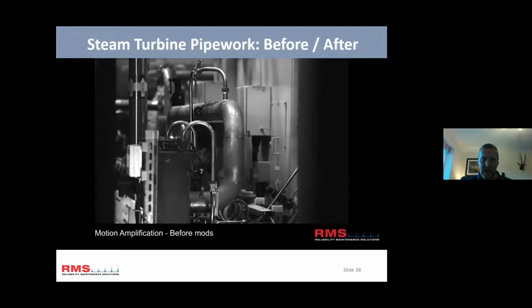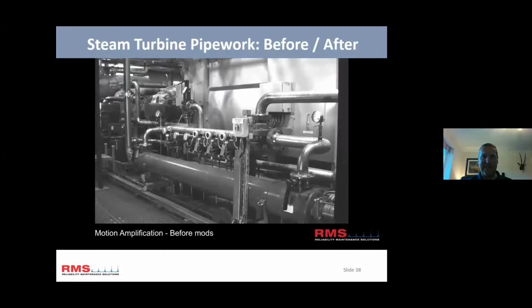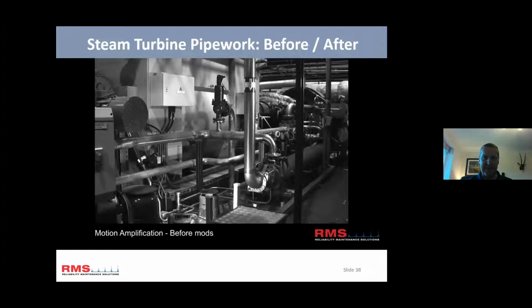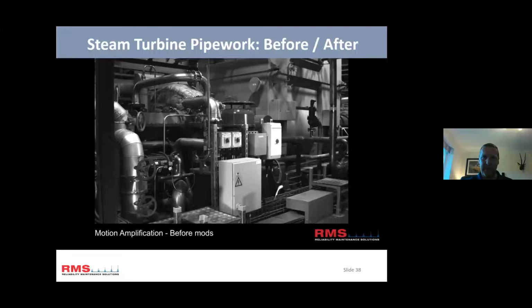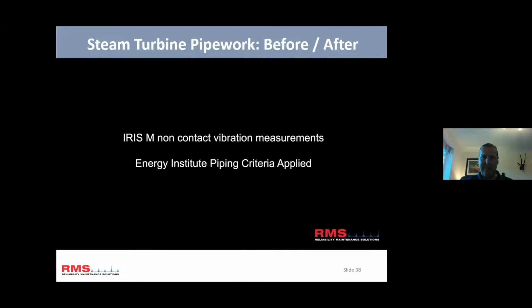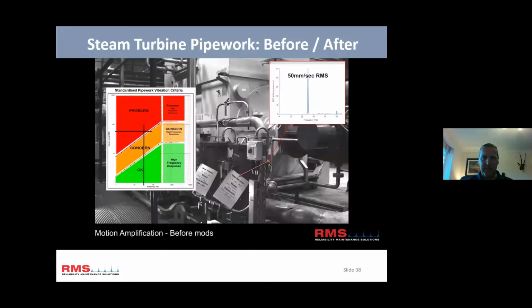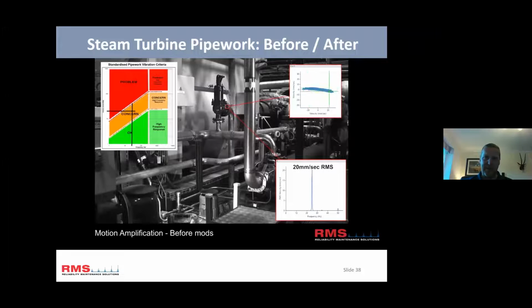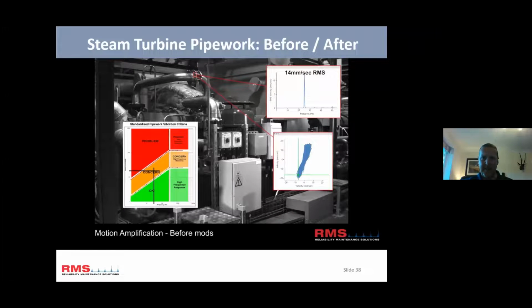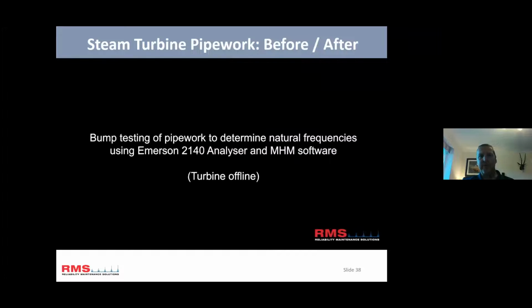So that's what you see with your eye, and then we motion amplify, and we can see it's more than just the little pipe at this end. There's a lot of pipework motion. Generally, when you see this movement in the video, it's normally excessive - we sort of know just by seeing it moving. So we did some measurements and plotted against the criteria, and again it was in the concern bracket, 20 millimeters per second there. Left alone, this can certainly cause problems down the line.